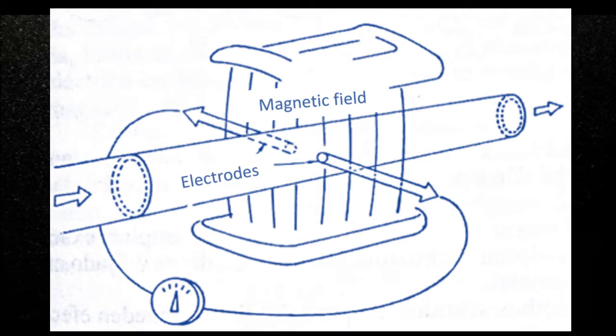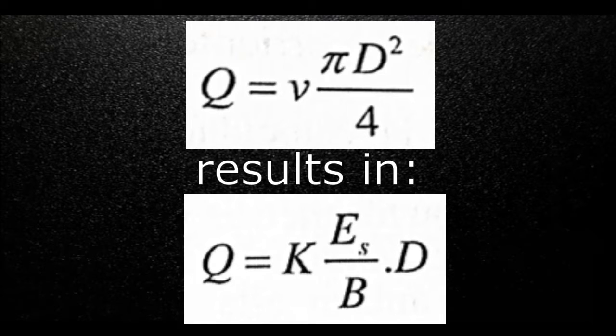To obtain a signal that depends only on speed, the influence of these three factors must be eliminated. In the magnetic flow method, the conductor is the liquid and the generated signal is captured by two electrodes, flush with the inner surface of the tube and diametrically opposed. The generated signal depends on the speed of the fluid and the density of the magnetic field, which is influenced by the line voltage and the fluid temperature as indicated by these formulas. To obtain a signal that depends only on speed, the influence of these three factors must be eliminated.